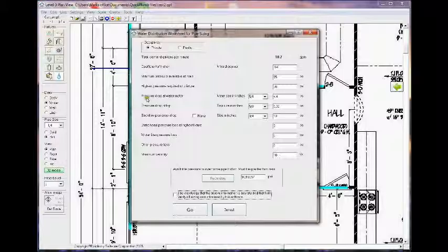The pressure drop of a 5/8 water meter at 10.7 gallons per minute is 4.4 psi. The pressure drop due to the 5/8 tap is 5.38 psi at 10.7 gallons per minute.